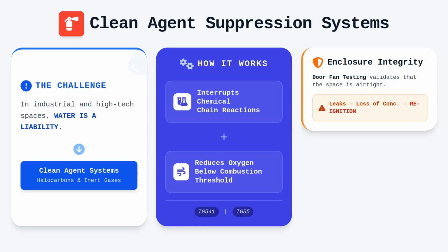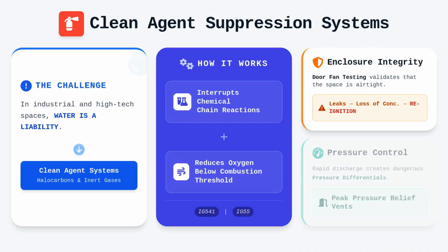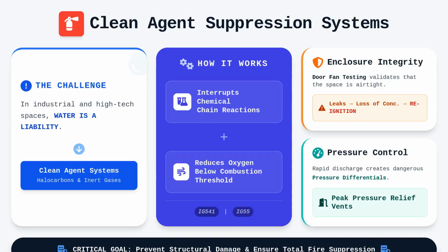When evaluating these systems, you must move beyond basic coverage and focus on the enclosure integrity. An enclosure must be sufficiently airtight to maintain the required design concentration for the specified holding time, which is validated through door fan testing. If the enclosure lacks integrity, the agent will leak, causing the concentration to drop prematurely and allowing the fire to reignite. Furthermore, the rapid discharge of gaseous systems creates pressure differentials, necessitating the installation of peak pressure relief vents to prevent structural damage to the enclosure walls.